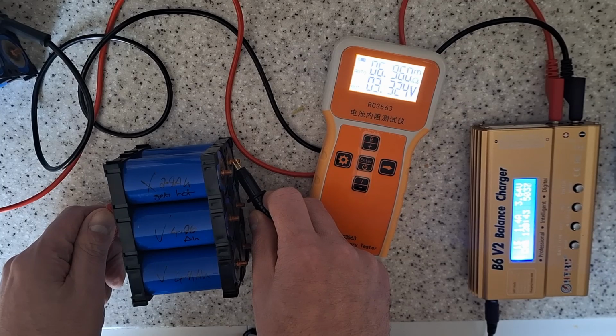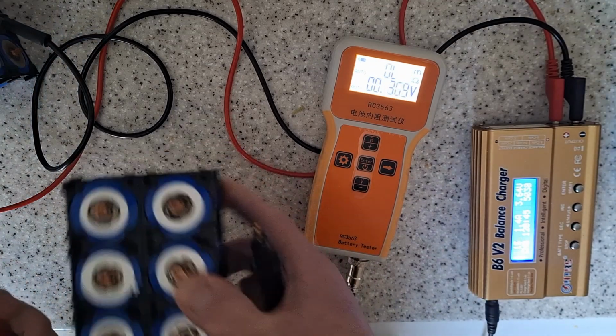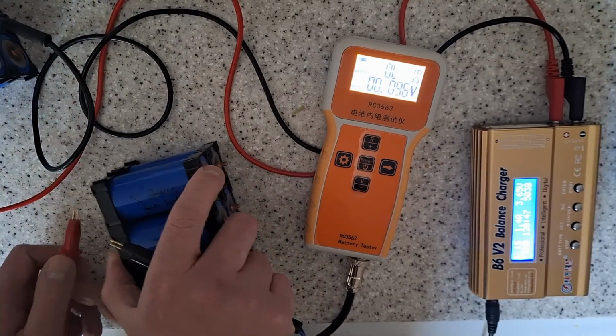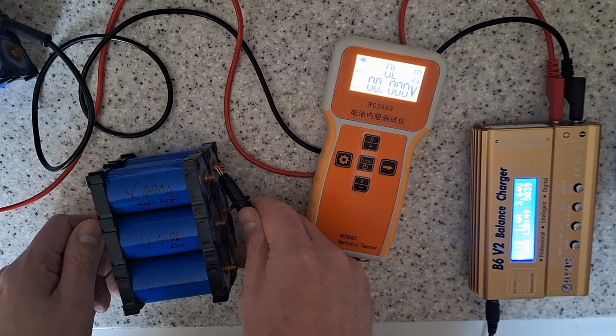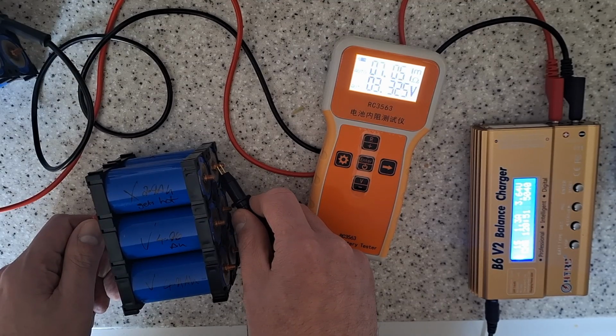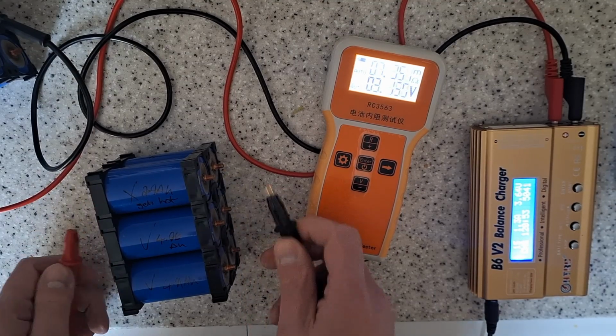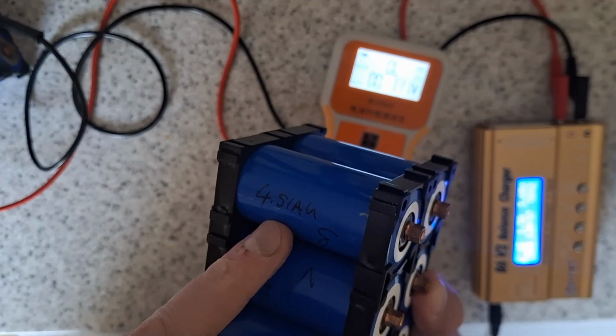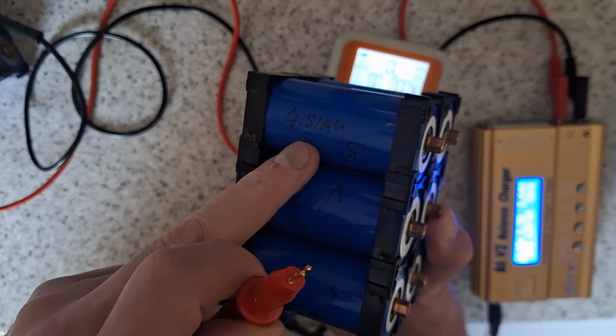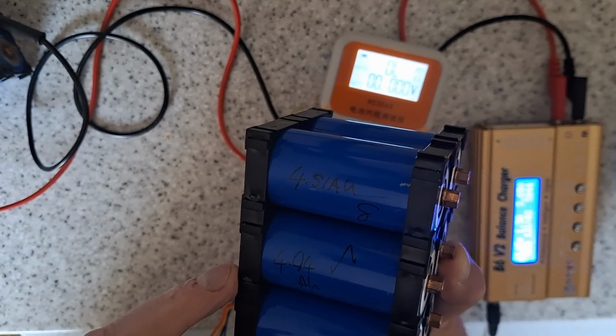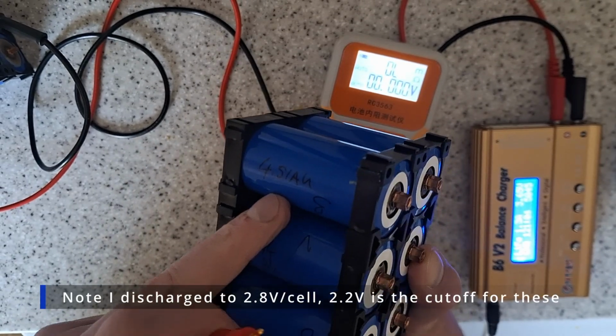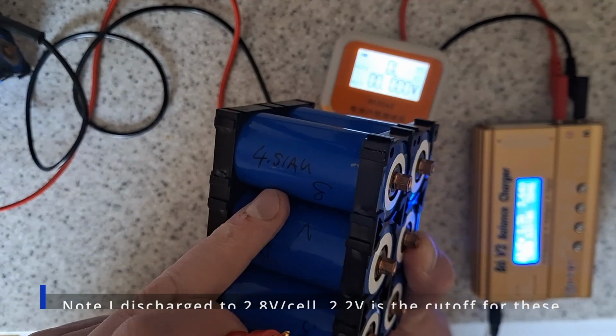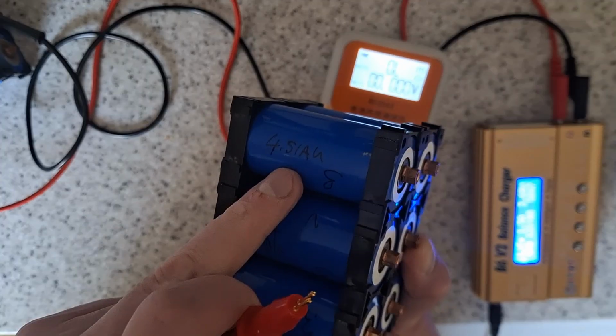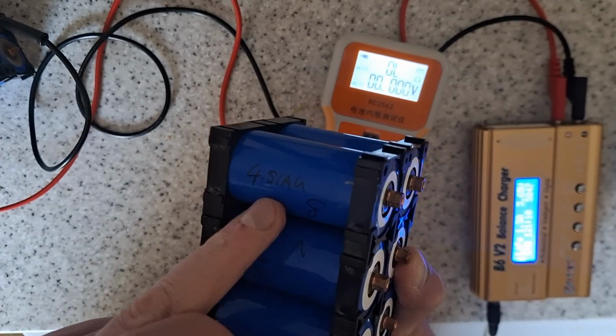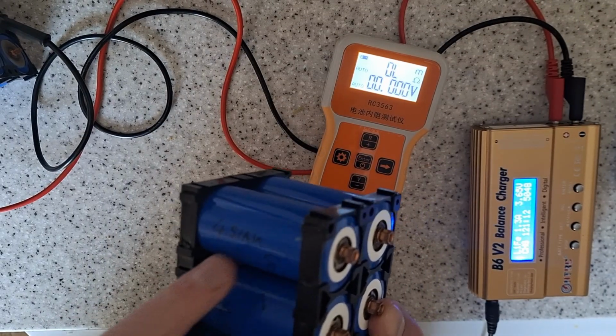That's 6 milliohms - 6.96, yeah, that's a good one as well. But the capacity on that one is only 4.51 amp hour, slightly out of spec. All the others are about 4.9 or just over 5 amp hour at 2.8 volts per cell. This one's given 4.51 amp hour, so it's slightly out of spec and I can't use it.